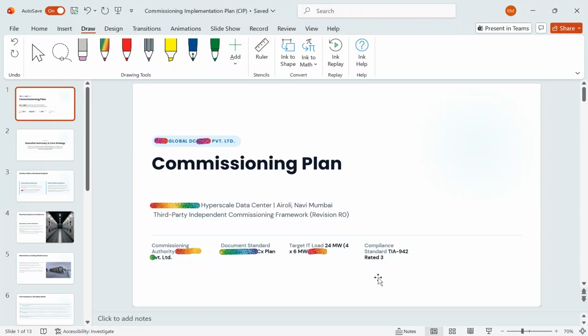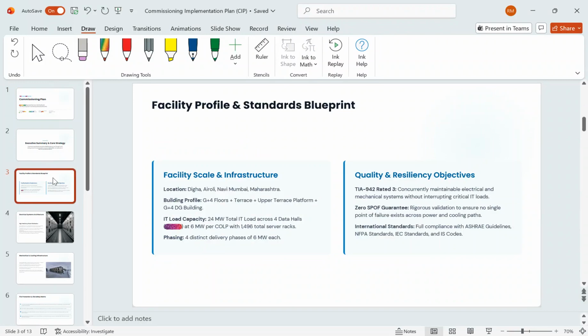Before doing this, the company needs to understand exactly what the data center facility is about. For this case, I have prepared a hypothetical data center. This is the facility profile, where the location of the data center is shown in Navi Mumbai. The building is G plus 4 floors, with a terrace. It has an upper terrace platform and a G plus 4 DG building. Total 24 megawatt of IT load and 4 data halls, 6 megawatt of data hall load with 1496 server racks. It will be executed in 4 distinct delivery phases, 6 megawatt per phase.